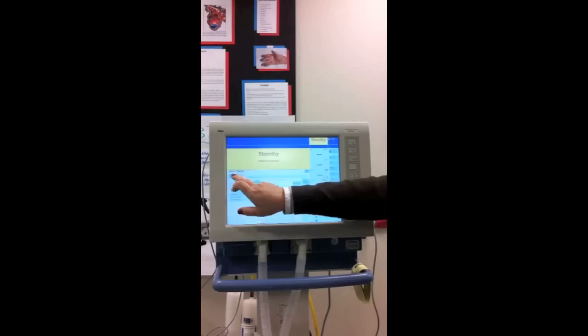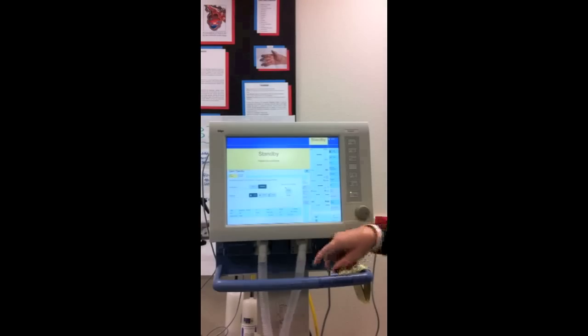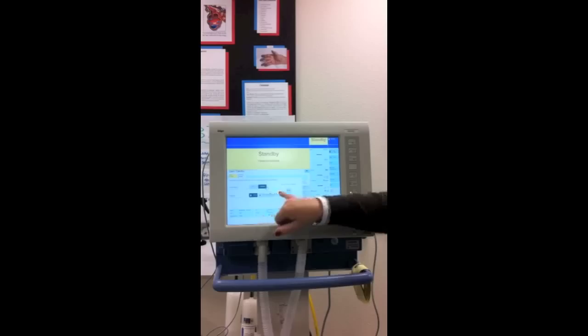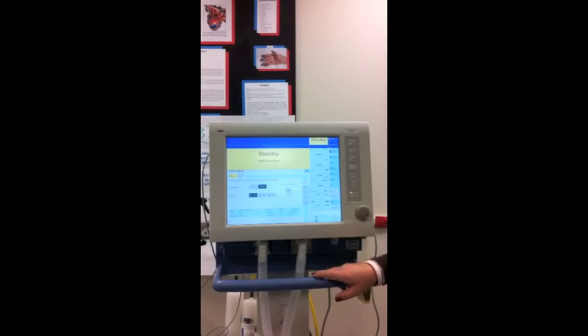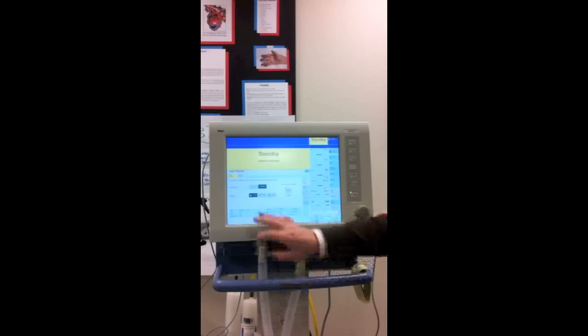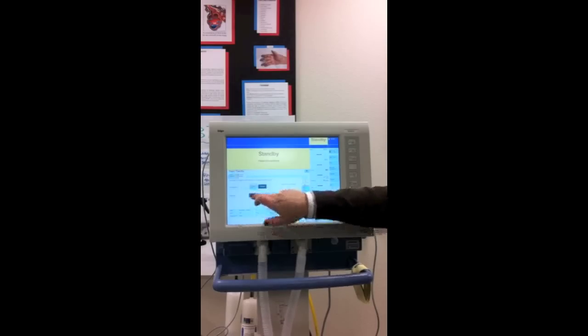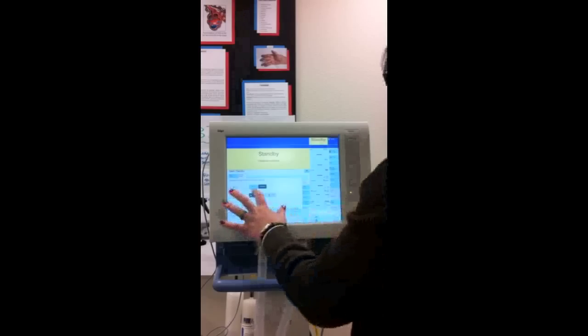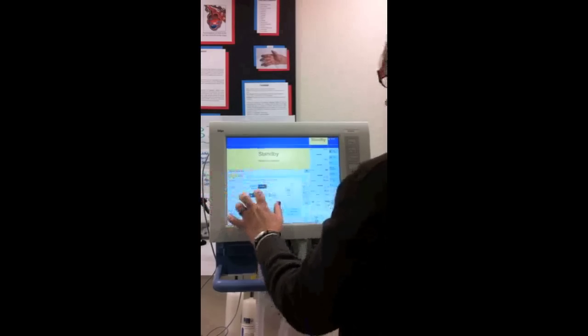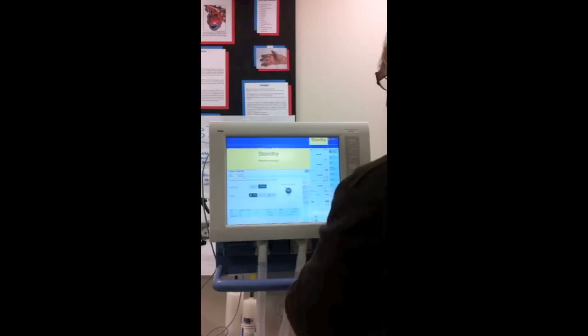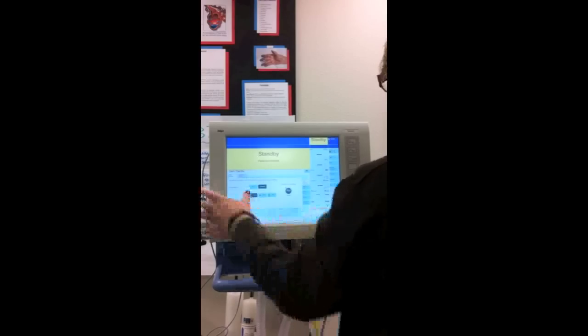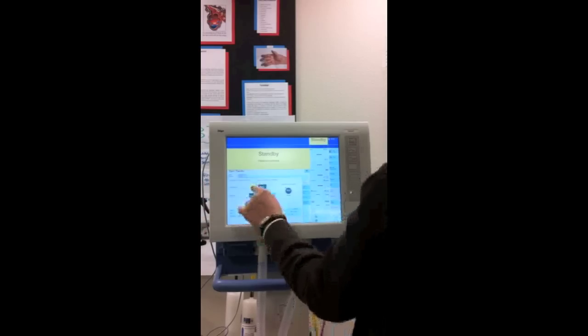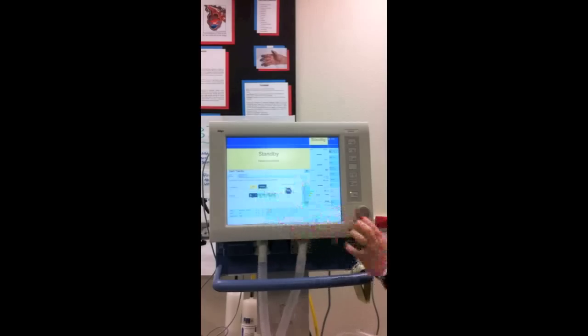So now if we go back to our new patient, we can set it up if we wanted to. There's adult, pediatric, neonatal again, ideal body weight, which we don't use. And it tells you what is currently set. So we're going to go to adult. Sometimes the screens are a little funny on this one. Adult. Come on. Okay. It wanted me to confirm it. And then start, and then the start will turn yellow. So once you did whatever you wanted to do right here, then hit start, and we'll go into ventilation. And we'll start ventilating.